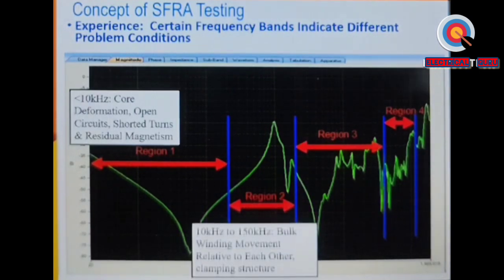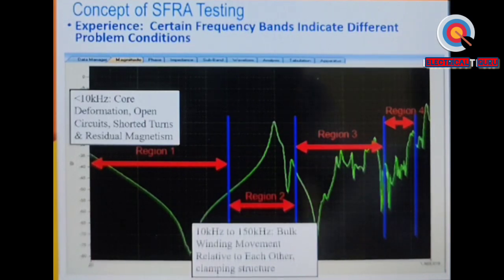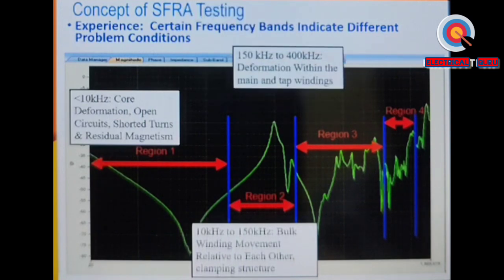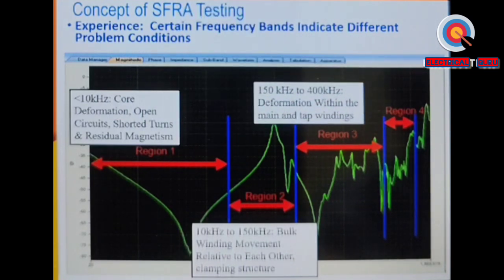Region 2 is from 10 kilohertz to 150 kilohertz. The bulk winding movement relative to each other, clamping structures. So if you see a distortion in the region of 10 to 150 kilohertz, you can say that there is some problem in the winding, or the winding is deformed, or relative movement is there in the winding, or a clamping structure is changed. So somewhere a movement has happened in the winding. Region 3 is 150 kilohertz to 400 kilohertz. Deformation within the main and tap winding. So if we find a distortion between 150 kilohertz to 400 kilohertz, then we say it is a deformation within the main and tap winding.